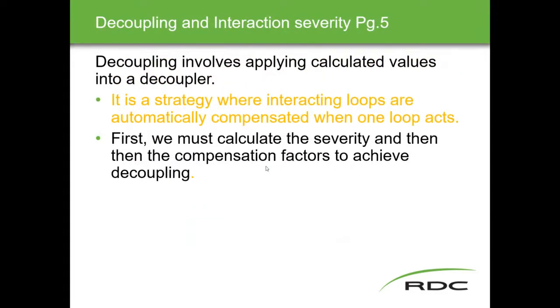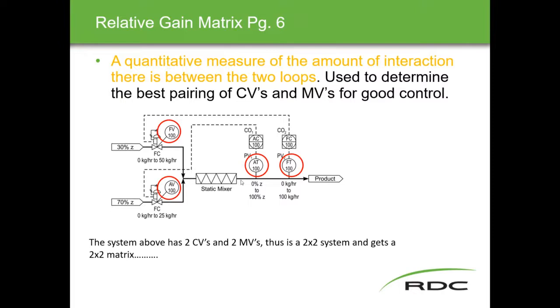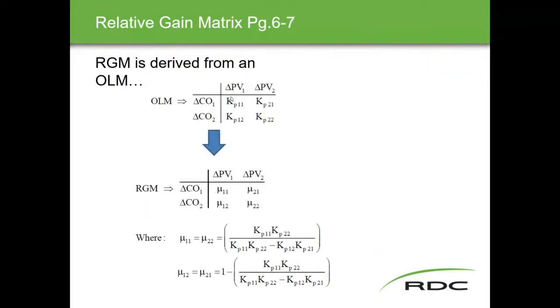Starting out with the calculations for the severity of loop interaction, from which we get the compensation factors to achieve decoupling. We look at the process variables PV1 and PV2 and the controlled variables CO1 and CO2. This system has two controlled variables and two manipulated variables — a two-by-two system — which gives us a two-by-two matrix. They can be bigger, but thankfully we only deal with two-by-two here.